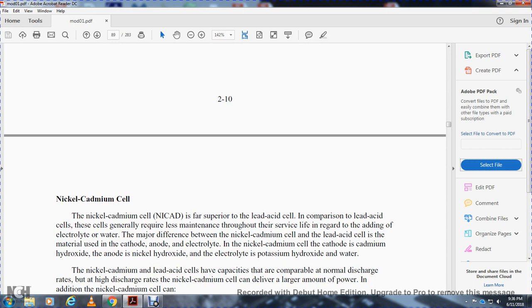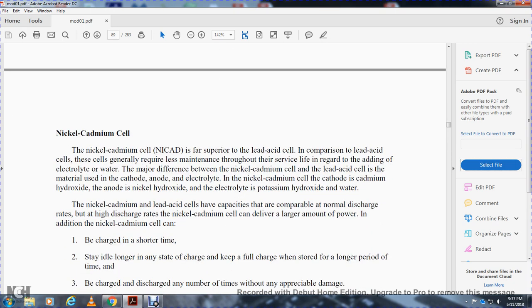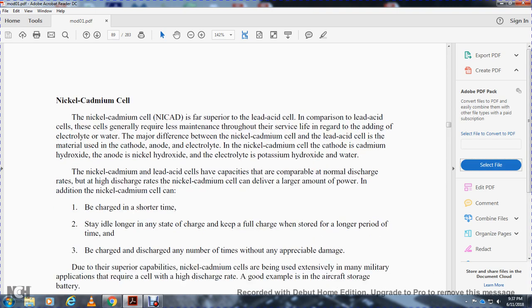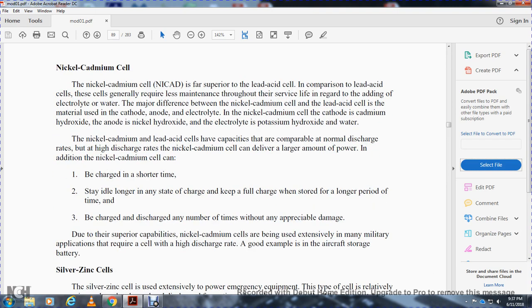Nickel cadmium (NiCad) is far superior to the lead acid cell and generally requires less maintenance throughout its service life regardless of electrolyte or water levels. The major difference between the nickel cadmium cell and the lead acid cell is the materials used for the cathode, anode, and electrolyte. In the nickel cadmium cell, the cathode is cadmium hydroxide, the anode is nickel hydroxide, and the electrolyte is potassium hydroxide and water.